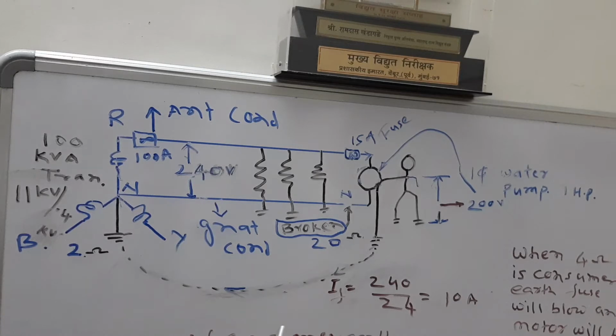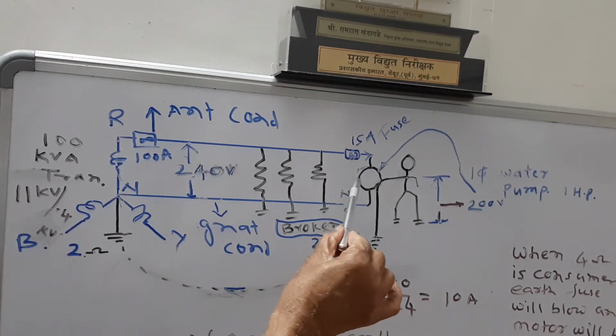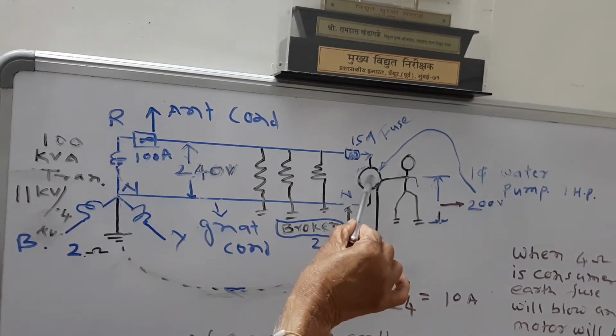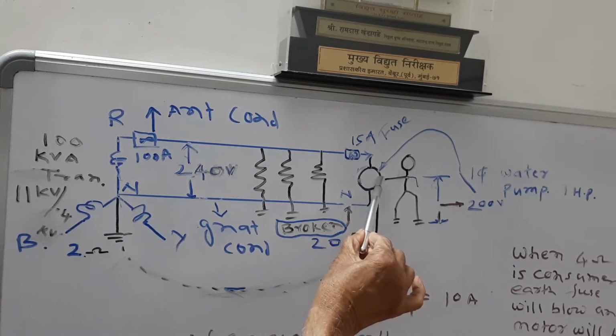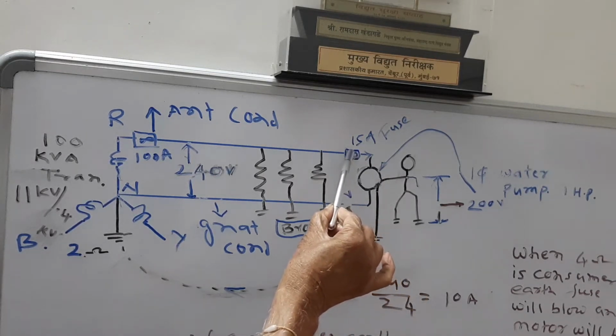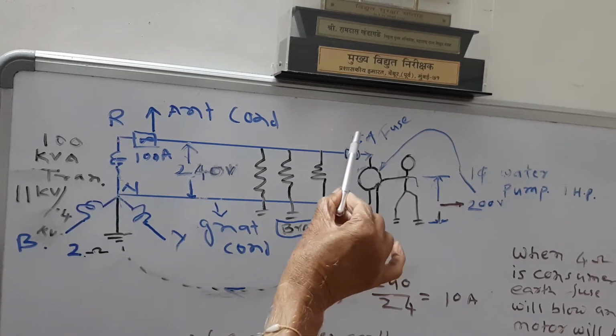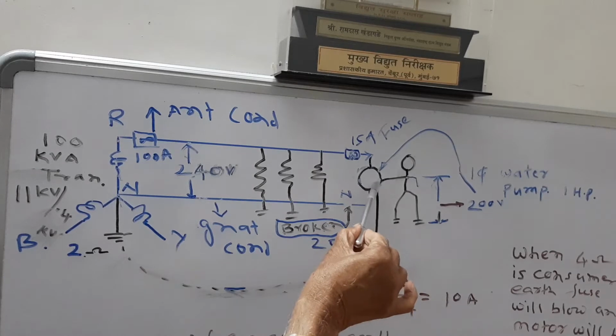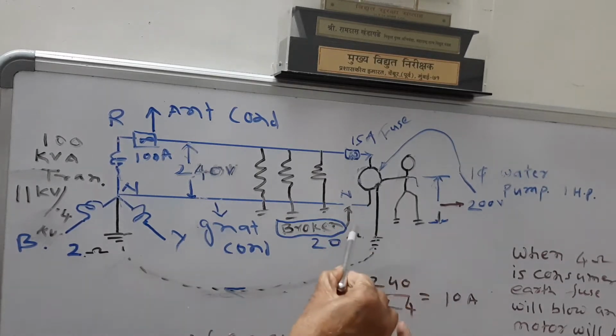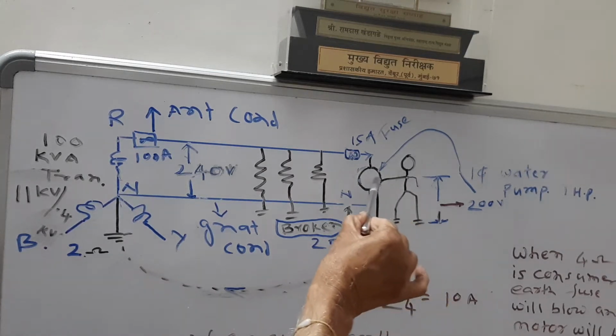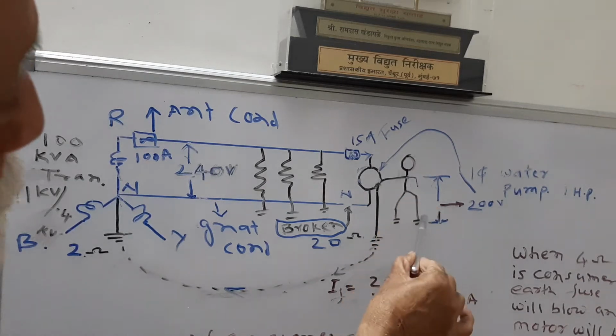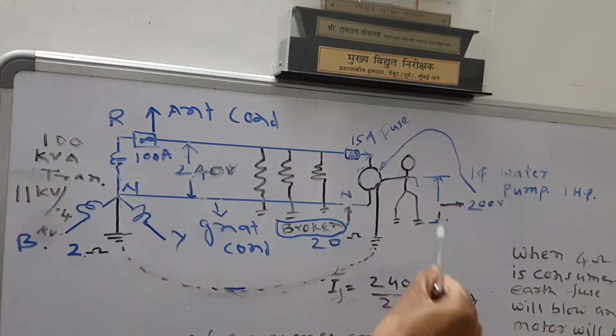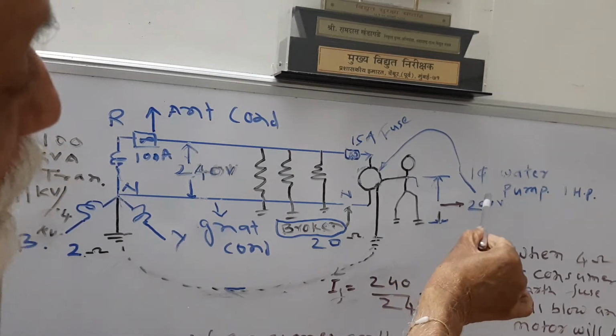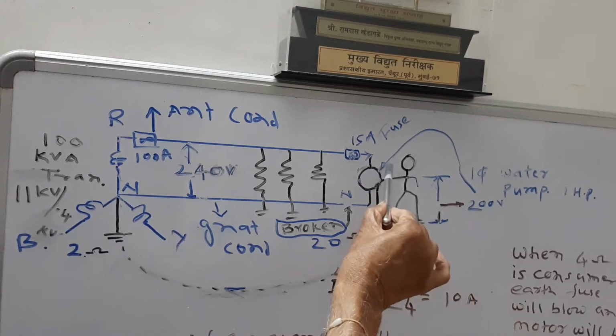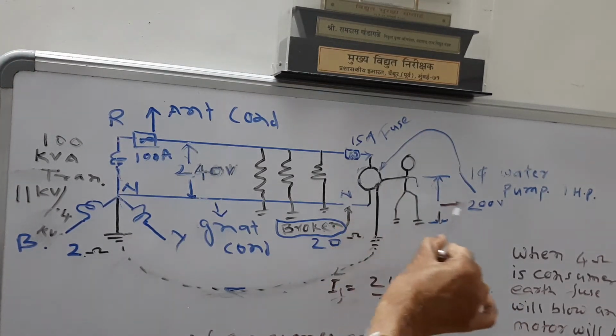Now, this person is not touching the frame, and as soon as the leakage current of this winding leaks to this frame, at that point only this fuse should blow. But why did it not blow, and why did the frame remain charged for a long period? And when this person came and touched it, he got a shock, and across him the voltage developed is 200 volt. Now I will explain how this 200 volt came across this person, and the frame has 200 volts.